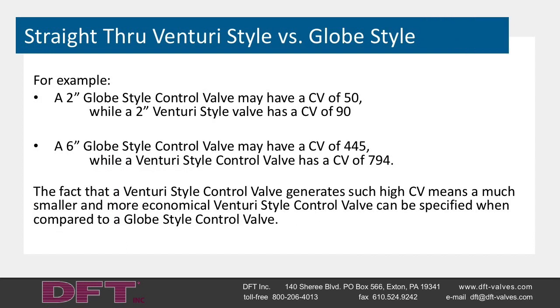Straight-through Venturi-style versus globe-style: Venturi-style control valves generate higher CVs than globe-style control valves. For example, a 2-inch globe-style control valve may have a CV of 50, while a 2-inch Venturi-style control valve has a CV of 90. A 6-inch globe-style may have a CV of 445, while a Venturi-style control valve has a CV of 794. The fact that a Venturi-style control valve generates much higher CV means a smaller and more economical valve can be specified compared to a globe-style.